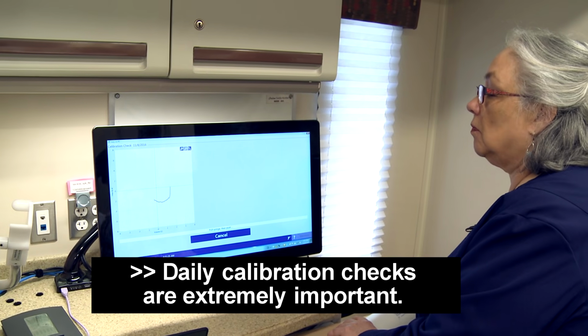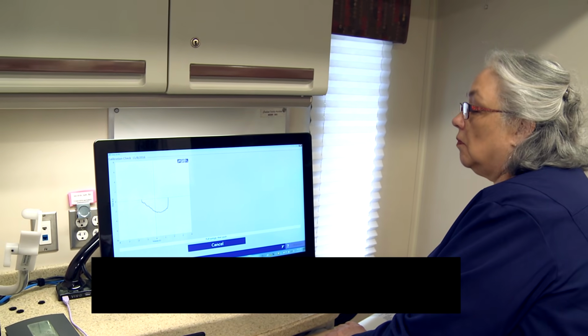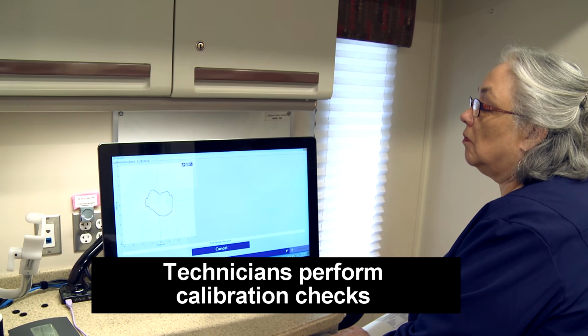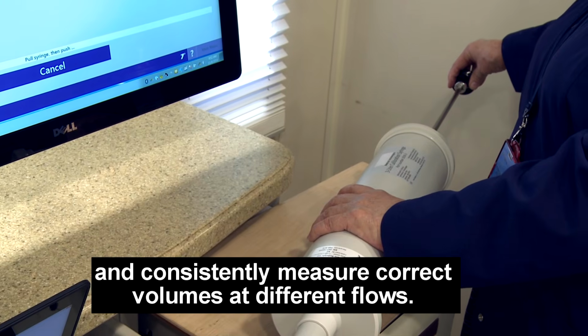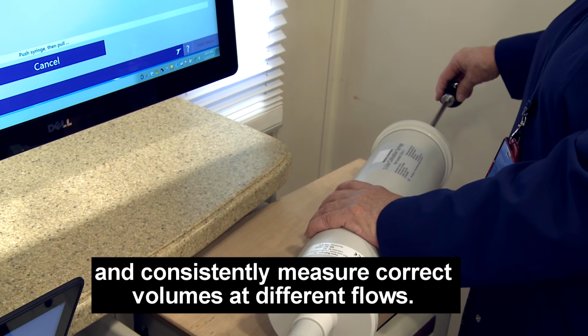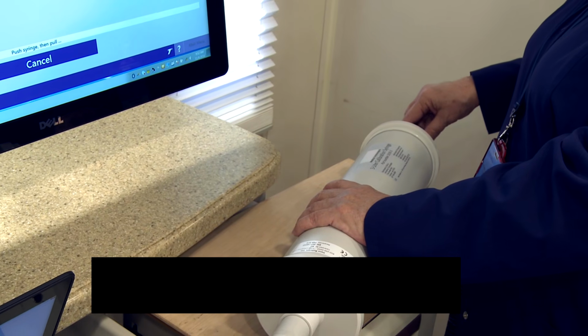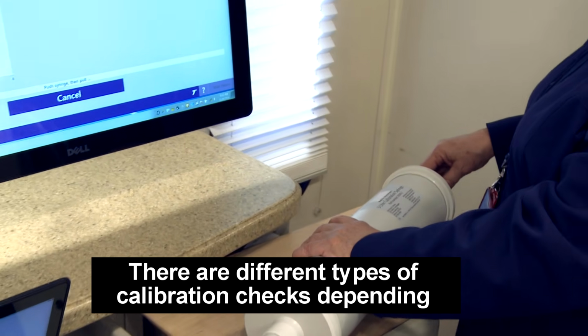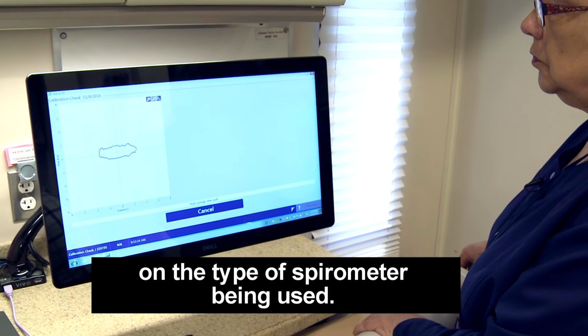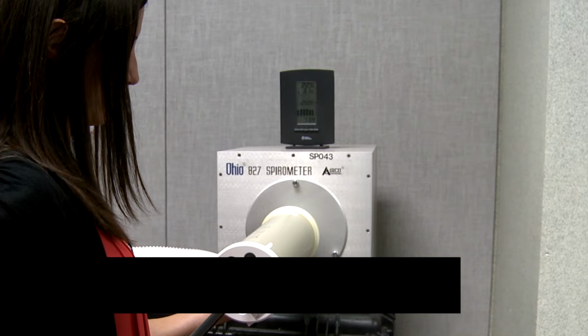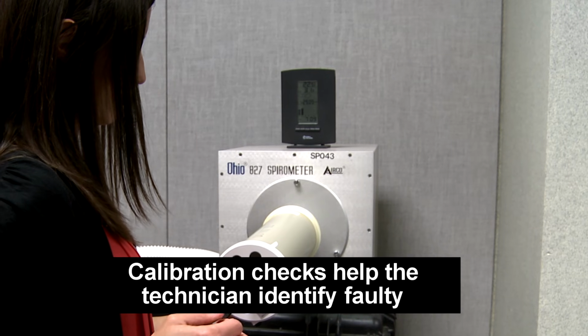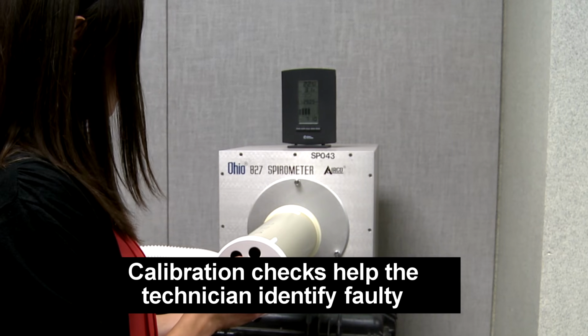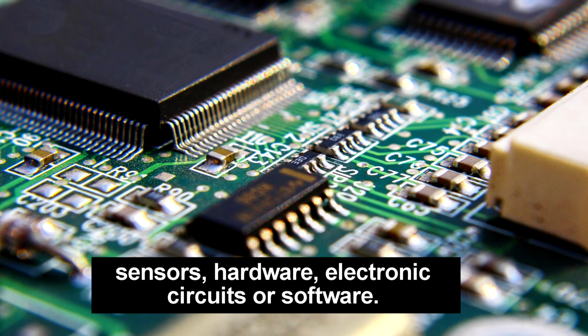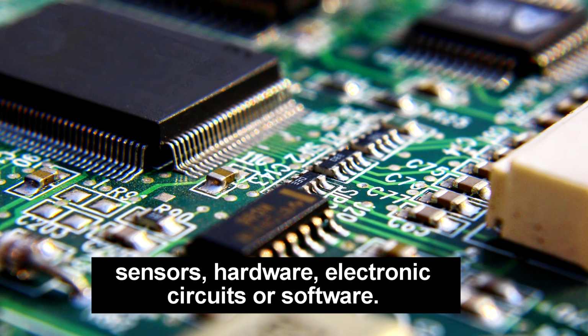Daily calibration checks are extremely important. Technicians perform calibration checks to make sure the spirometer is able to accurately and consistently measure correct volumes at different flows. There are different types of calibration checks depending on the type of spirometer being used. Calibration checks help the technician identify faulty sensors, hardware, electronic circuits, or software.